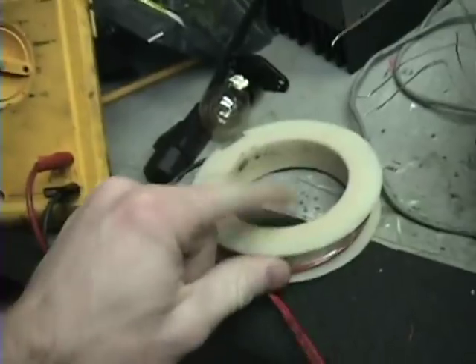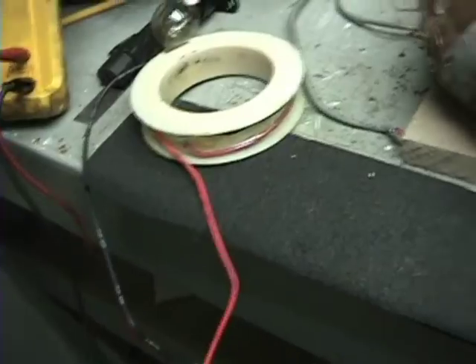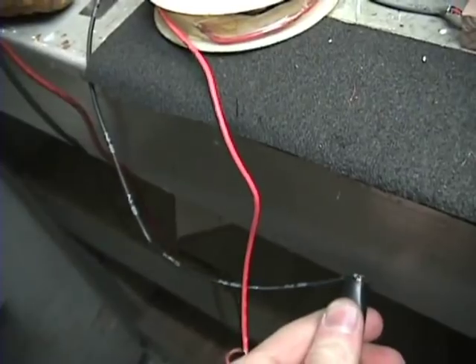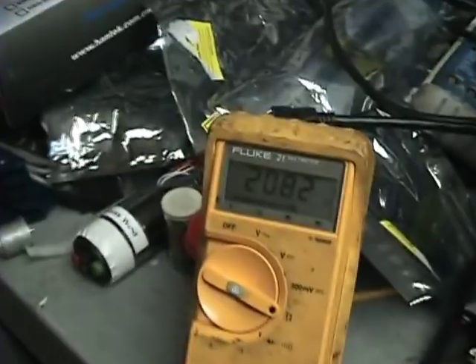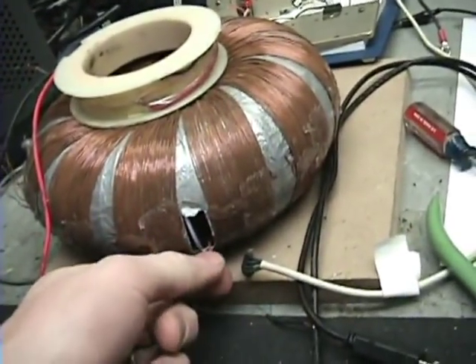The coil that I have right here that's exactly like it is approximately 2,000 ohms. So there you go — that's this coil here. I don't think this is going to affect it any. Basically what this means is that wherever my short happened, I still have 1,500 feet of wire. Somewhere in there it's shorted — it's only slightly shorted, but still shorted.